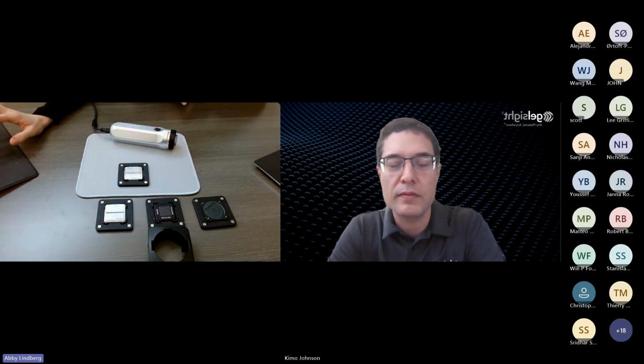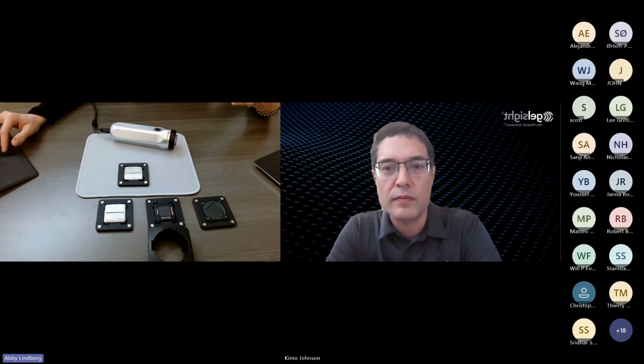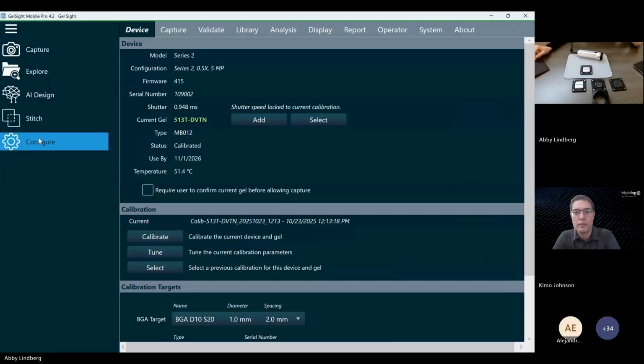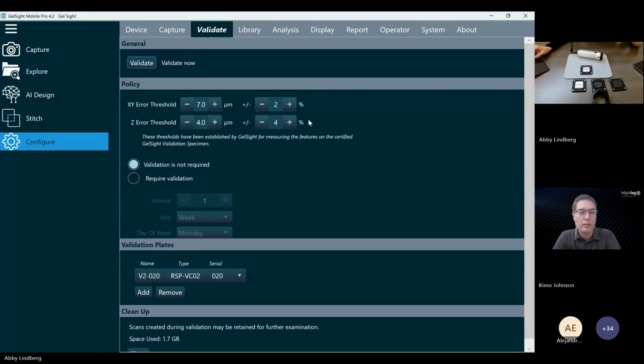Thanks, Kimo. I'll now walk through what running validation looks like in the GelSight software. Let me share that screen again. I'm going to click validate in our software here. Validation can be configured as a requirement, so that you can't take any scans until you pass validation. You could set this to be performed daily, weekly, monthly, or after a certain number of scans, so that you can't go on unless you're reporting within your tolerances.